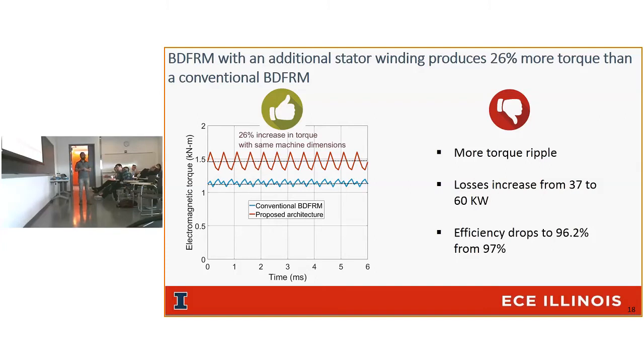Since I'm introducing more current in my stator slots, I'm increasing my current density, which leads to more copper losses. Also, with the introduction of another stator winding, I'm introducing a lot more flux density harmonics, which leads to more core losses. That's why the losses also increase from 37 to 60 kilowatts, and efficiency drops from 97% to 96.2%.